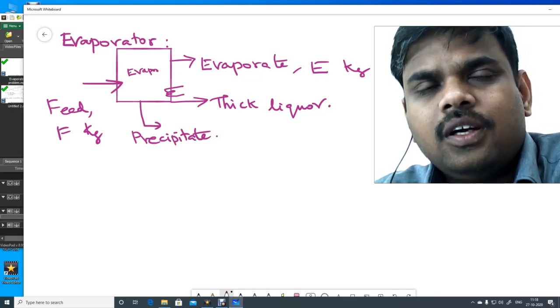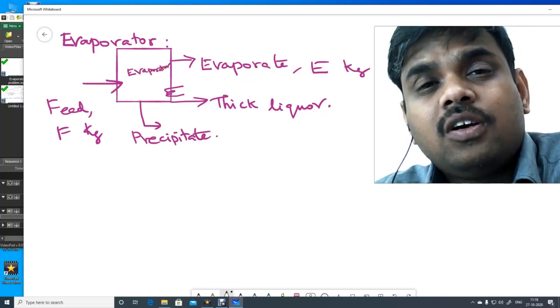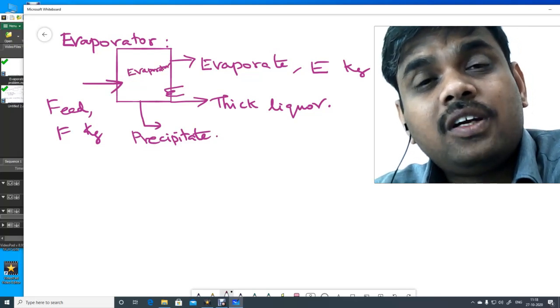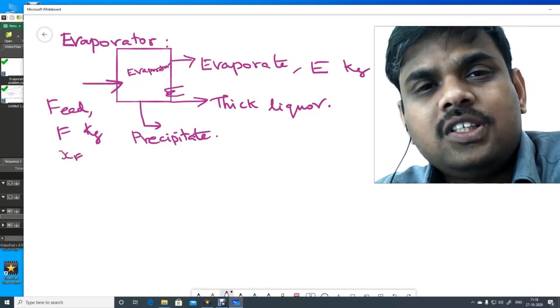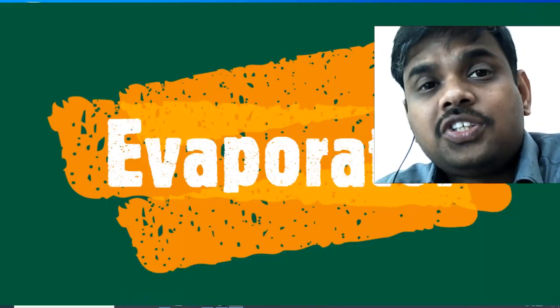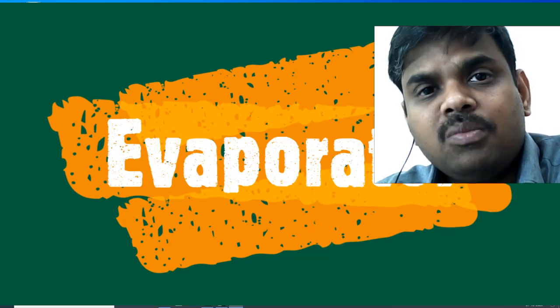Actually, the economy of an evaporator depends upon how much water is evaporated per kg of steam. Evaporator economy or steam economy in an evaporation operation is the number of kilograms of water vaporized from all the effects per kg of steam used or consumed.